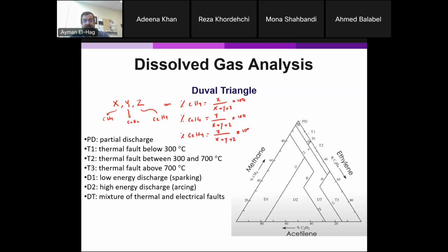Okay, so once you have found these, you bring them to this triangle. And you try to see these three points; they have to intersect at one single point. If it intersects at more than one point, it means that there is an error in the calculation. And then you can see here the triangle is split into seven different regions. You have the partial discharge, T1 to T3, which are basically our thermal faults, and D1 to DT, which are basically electrical faults. So you see where this point of intersection is, and then you can figure out what is the type of the fault that happened inside the transformer.